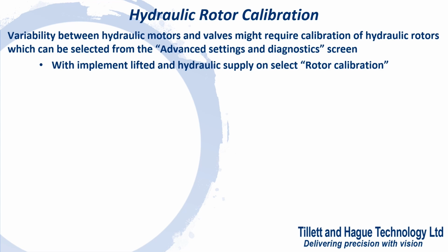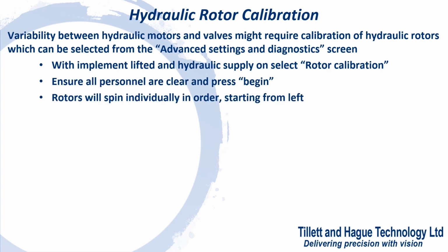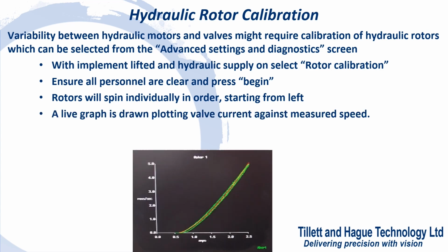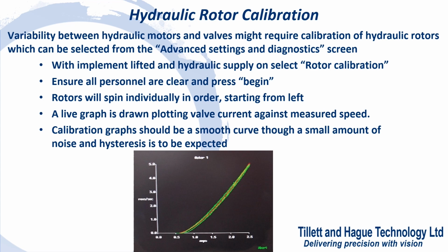Each rotor will ramp up in turn, starting from the left. The calibration test plots and records valve current against rotor speed output. This information is used to automatically calculate calibration parameters for each individual rotor. Calibration is affected by oil viscosity, so it's best done at a normal operating temperature. A smooth curve should be displayed without too much sensor noise, though a little hysteresis is to be expected.